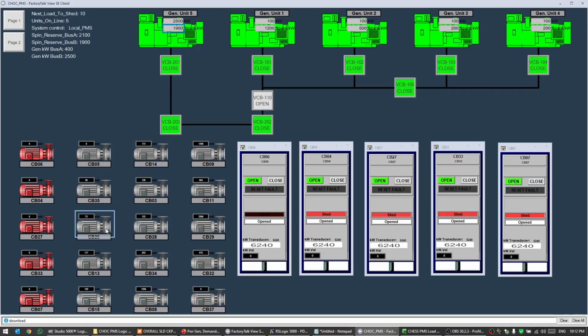Now I can see all 5 get shed. So I could assume that this testing setup can be used to test out the modified logic. Feel free to contact me so I can set up this testing setup so you could control it remotely.